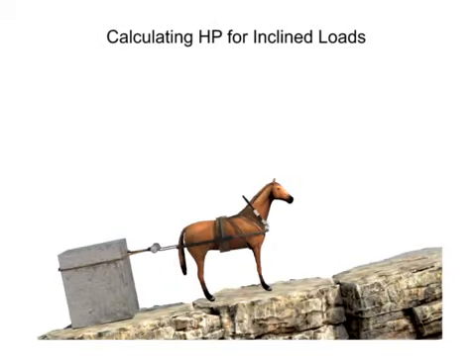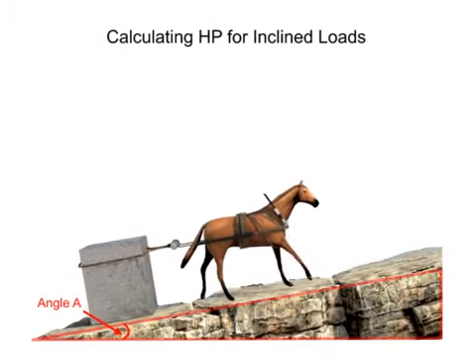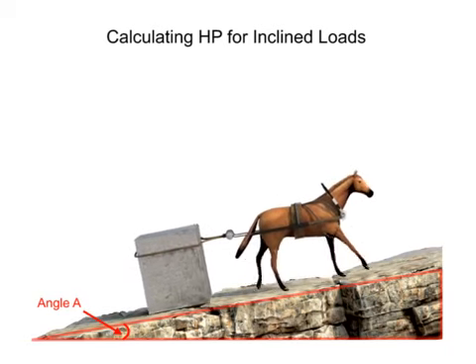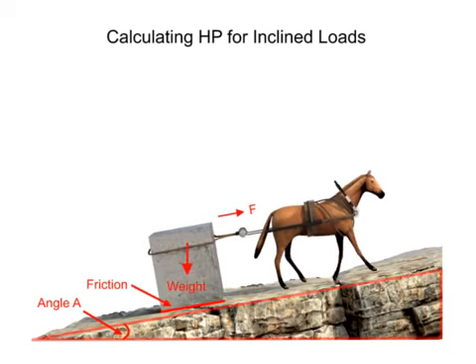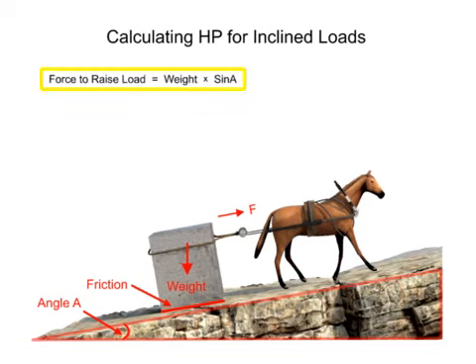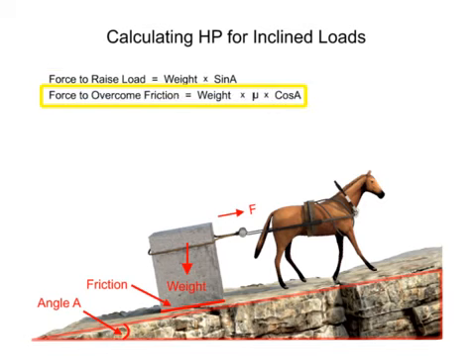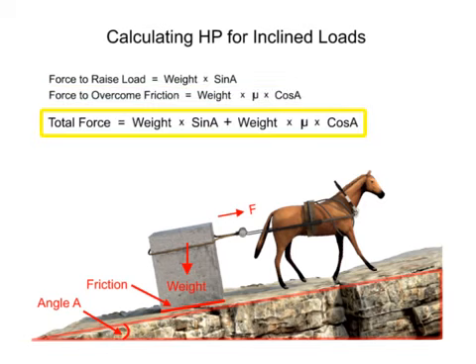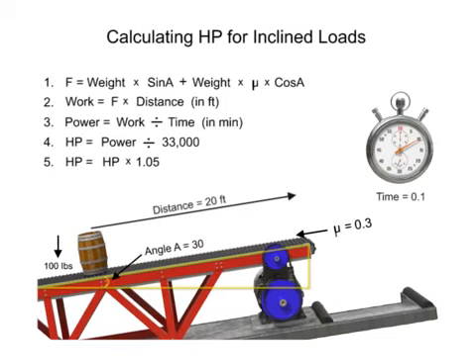If the distance to be traveled isn't on a horizontal surface, the angle of the surface must be taken into account. To determine the total force required, we must add the force required to raise the load to a higher elevation with the force required to overcome friction. The total force is equal to the weight times sine A, plus the weight times the coefficient of friction times cosine A. Once these two forces are combined, we can continue with the same steps used previously to calculate the size of the motor required.